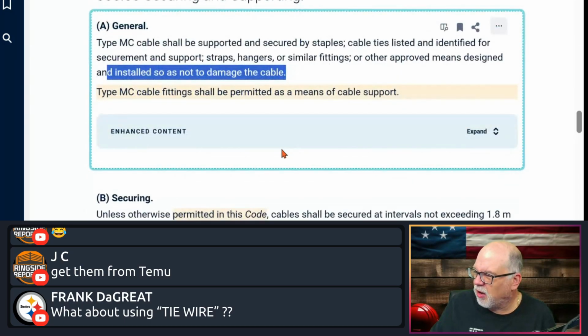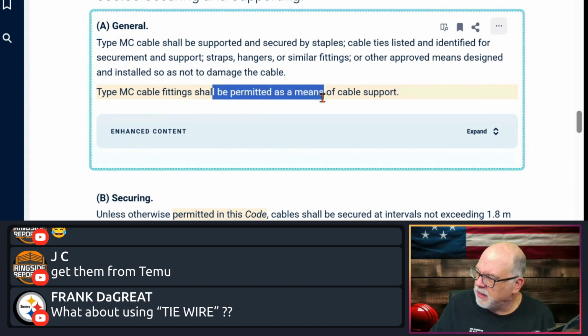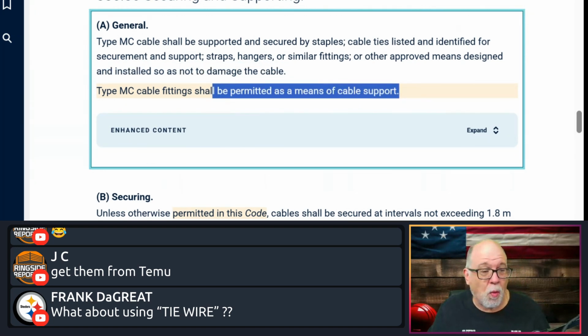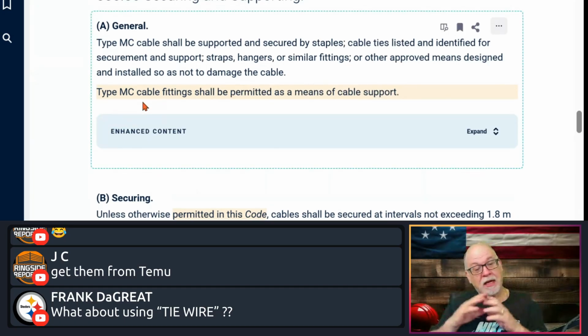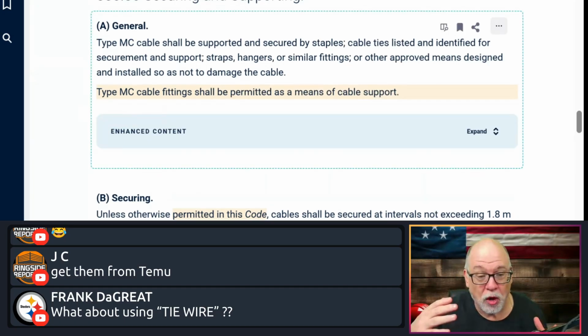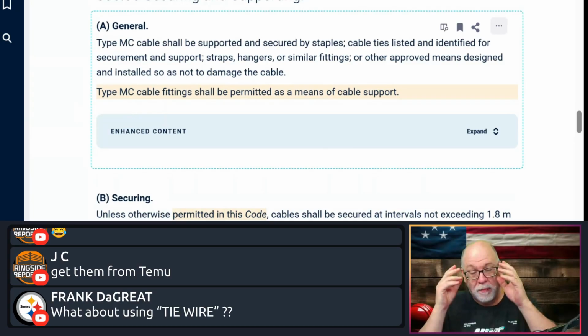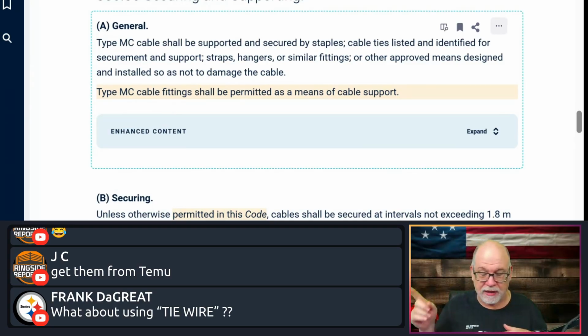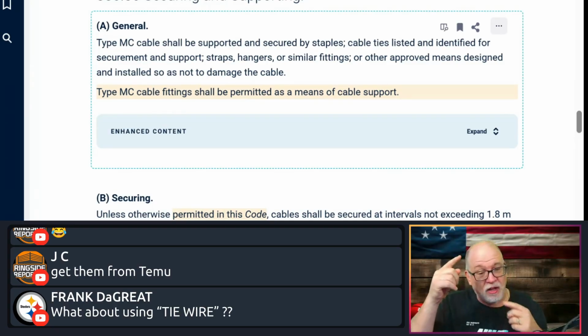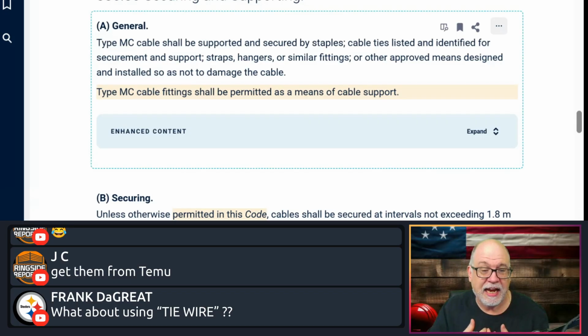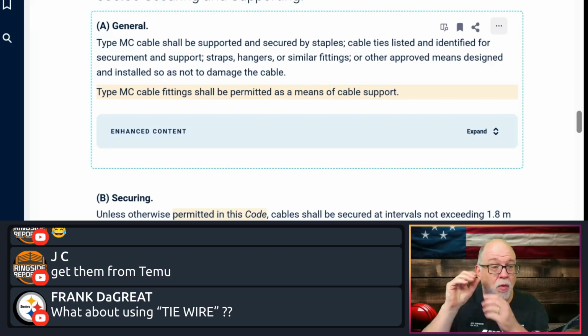Okay. Also, it says the MC cable fittings shall be permitted as a means of cable support. So why is that statement important? Why is that in gray? Because if I have some unsupported MC cable going from a box, let's say down to a luminaire, and we're going to look at that in a minute. If I have this unsupported piece, then it says it has to be secured within, let's say, 6 feet. It is considered secured when it comes to the cable fitting, right?